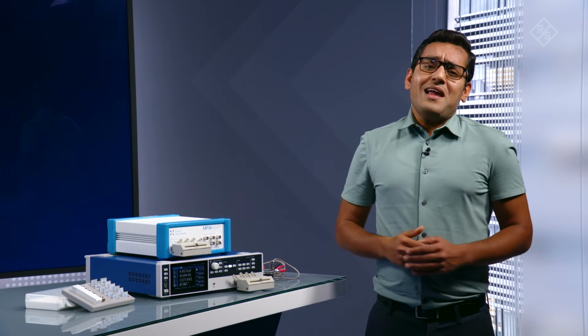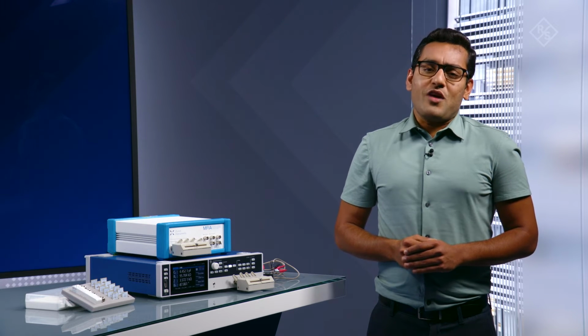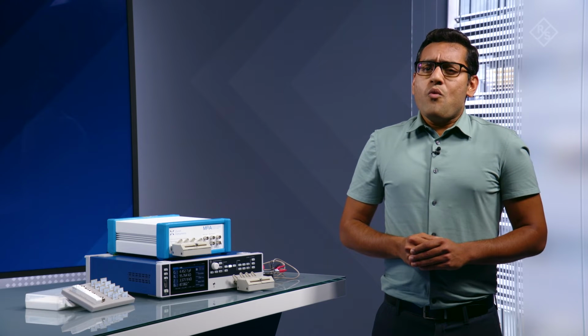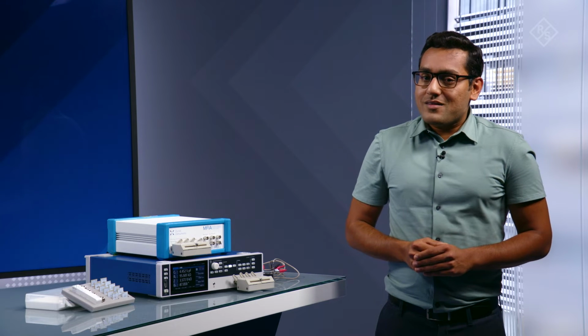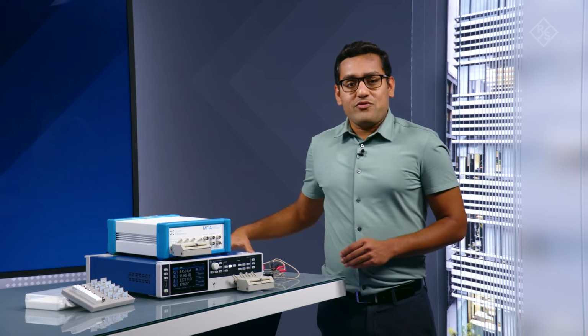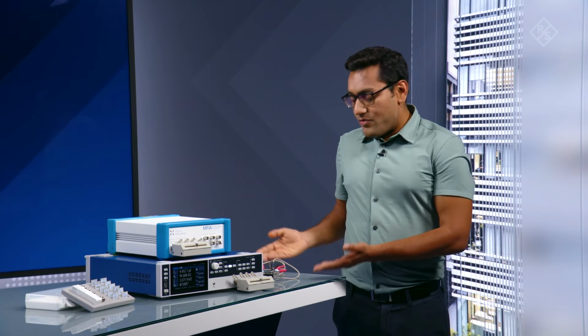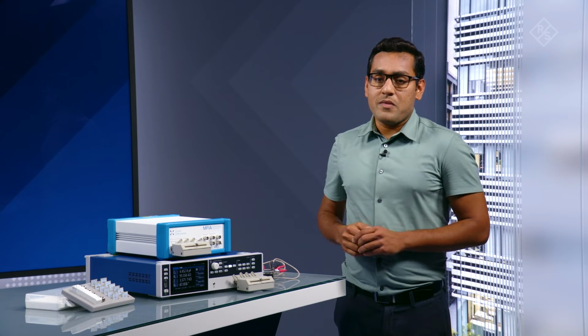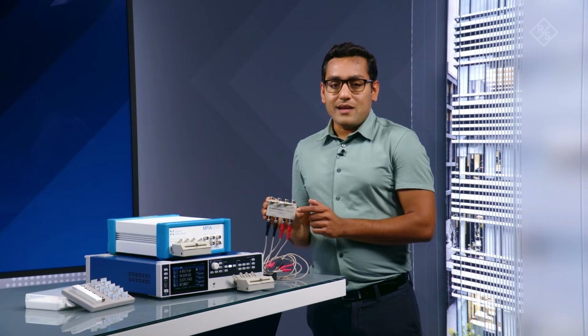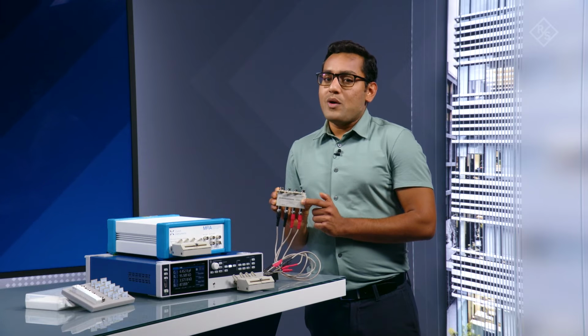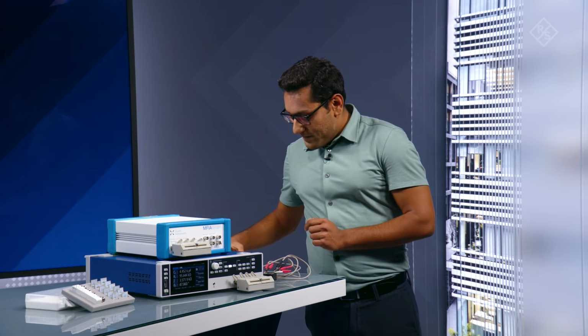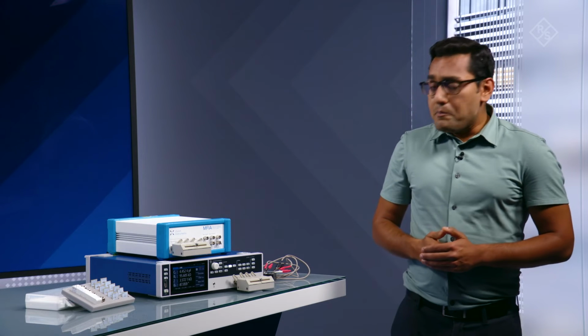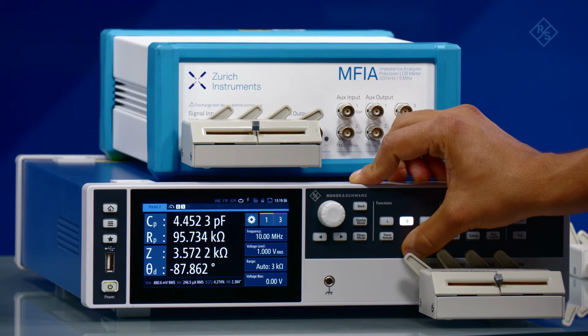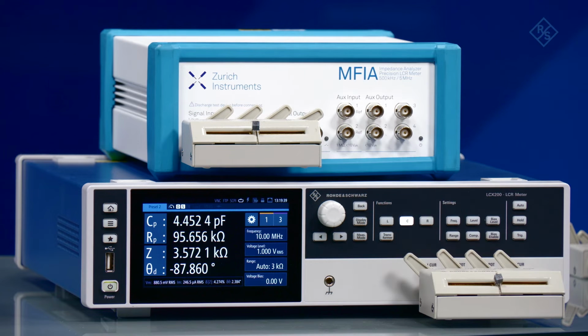Earlier in this webinar, Elizabeth gave you a lot of information about transformer testing. What if you want to do transformer measurements? The LCX-Z5 transformer test cables are a perfect measurement accessory for this purpose. Simply follow the circuit diagram printed on the test fixture when connecting the transformer, and press the transformer mode key to read the turns ratio and the mutual inductance values off of the LCX screen.